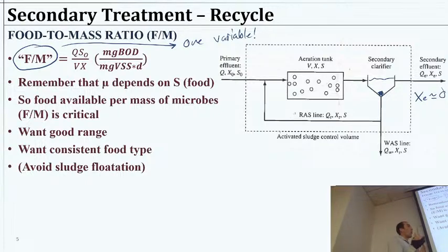And we also really, really need to recycle bacteria cells so that we can keep the function of our aerated chamber working, to keep the food and mass ratio correct. So if microbes start floating and making like a scum layer and bubbling up and being filamentous and stuff, this does happen sometimes, and suddenly they're leaving, well, we no longer have the recycle, so our bacterial mass in our system drops quite a bit, and now we are not treating nearly as much as we should be.